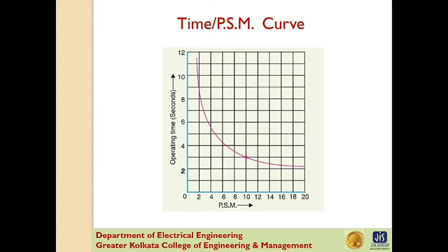Now, it is evident from this figure that at lower values of overcurrent, the time of operation varies inversely with the current, but as the current approaches 20 times full load value, the operating time of the relay tends to become constant. This feature is necessary in order to ensure discrimination on very heavy fault currents flowing through the sound feeders.